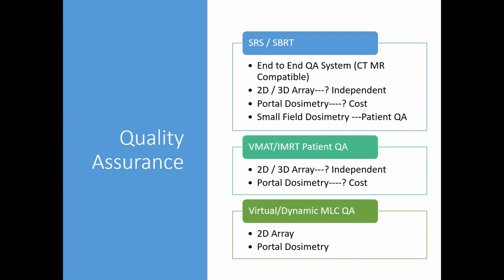That would be an independent solution, but it is time consuming. Setting up a 3D array and then getting results will end up being something like a 1 hour job. If you have portal dosimetry, it's a cost thing, but this is very easy. You will be getting results in maybe 10 minutes, but this is not an independent system, so we need to make choices by ourselves. And certainly we need a small field dosimetry system for the patient QA, where we will be checking point doses at different points. If we are having a standard LINAC with VMAT and IMRT, again, a 2D or 3D array is required and portal dosimetry is required.